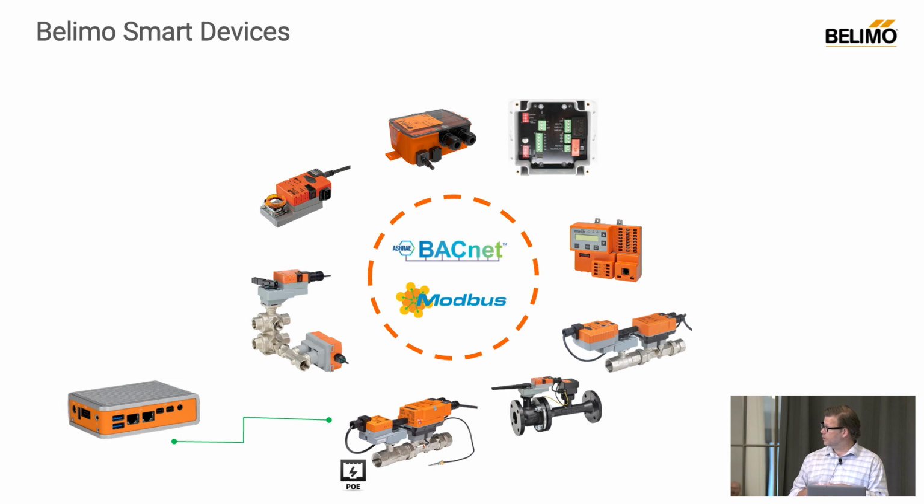This is remote fire smoke damper testing. NFPA, I think two years ago, now allows you to remotely test fire smoke damper actuators. So you send BACnet discover, bring in the objects. There's one object, command, you send a test. It goes through its paces, opens and closes, hits the various contacts, comes back and gives you a yay or nay.